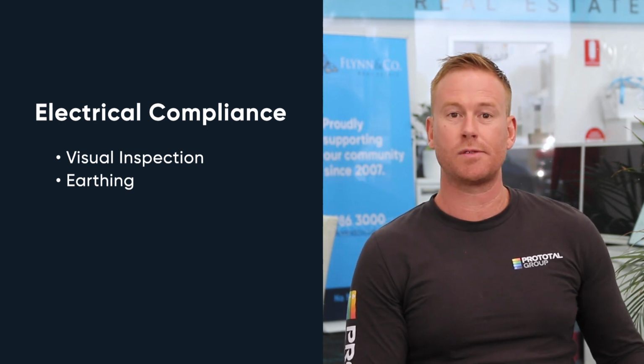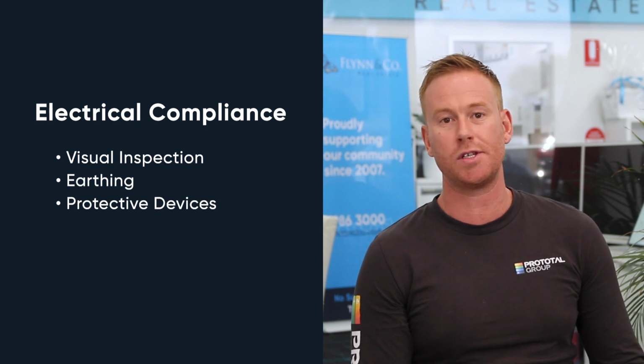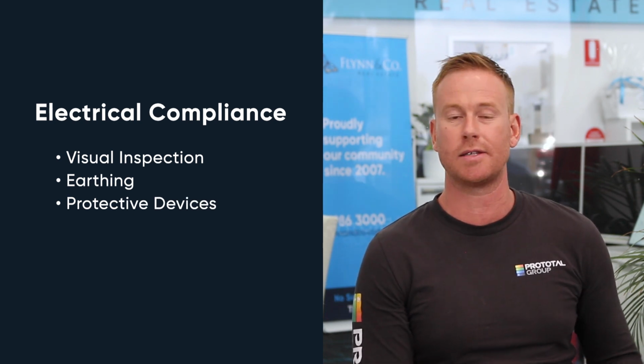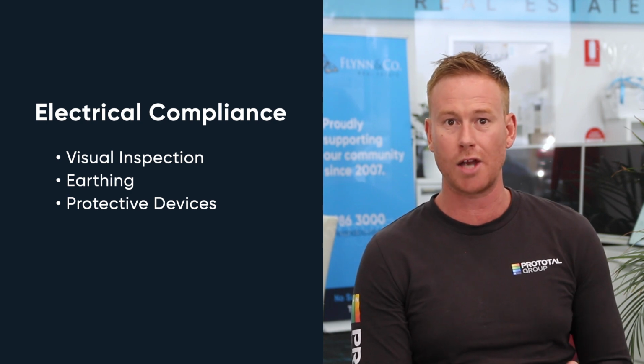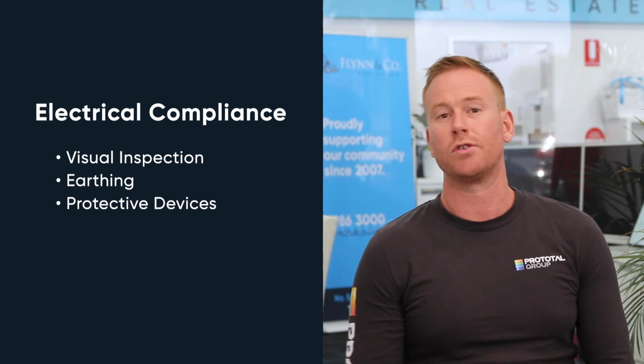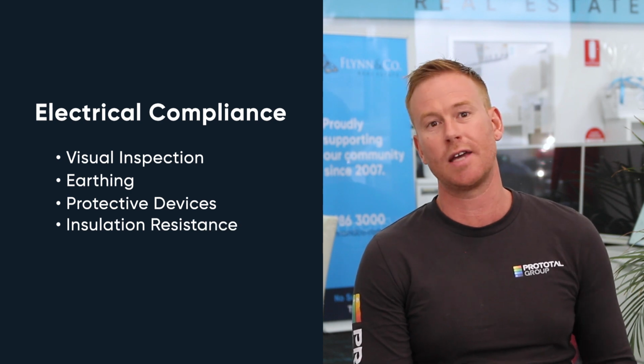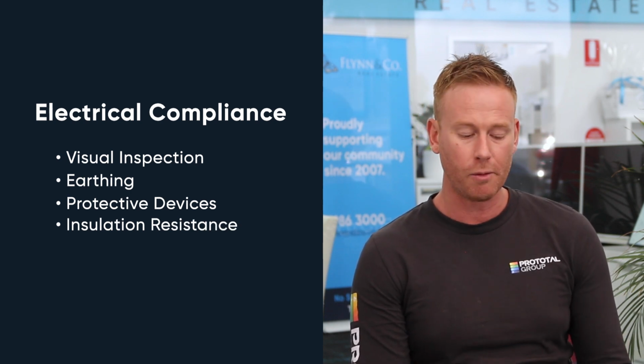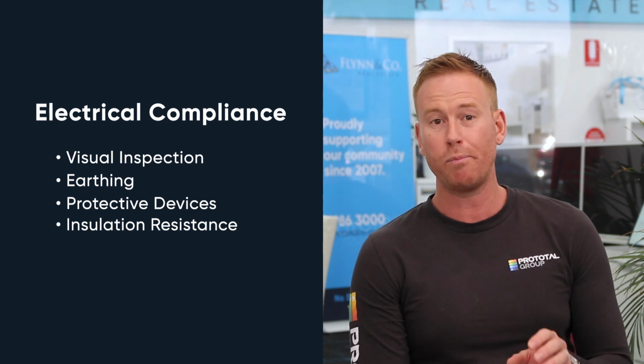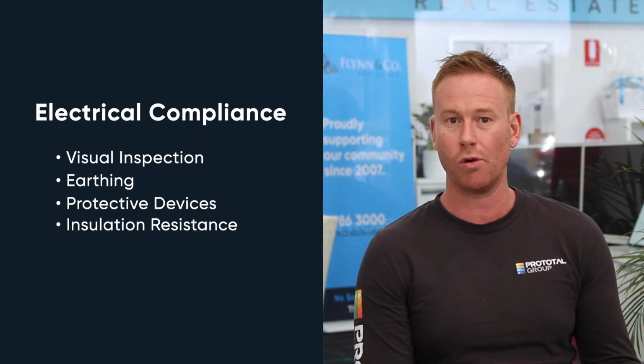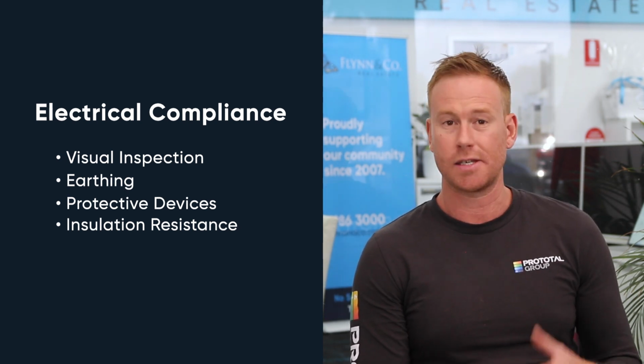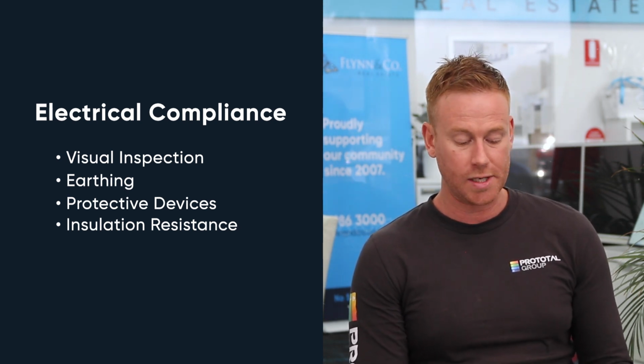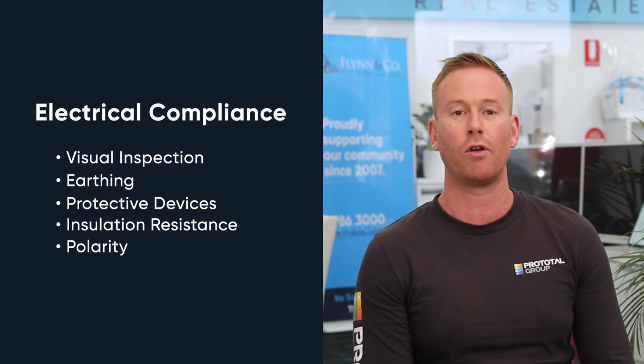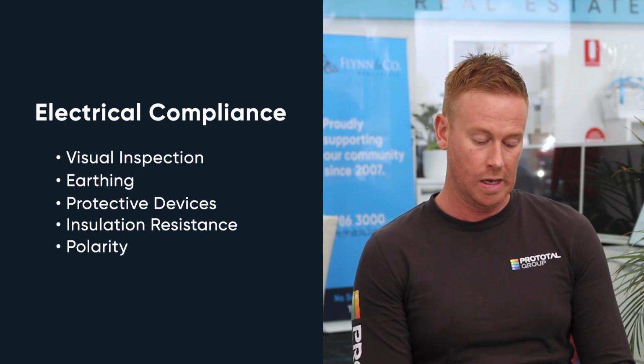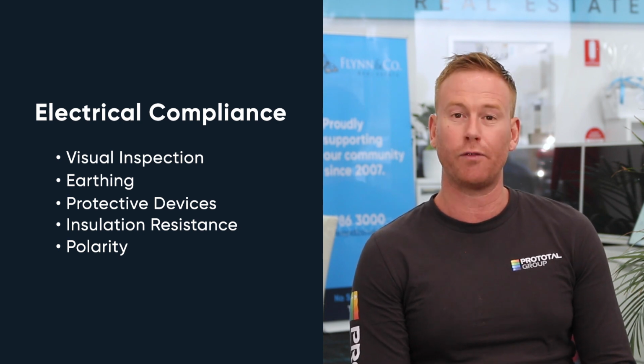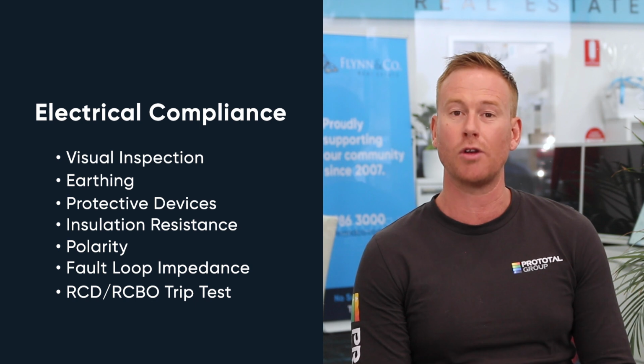We run through a number of steps: protective devices, your safety switches, circuit breakers, the integrity of those, and the related tests. We also do insulation resistance testing to test the integrity of your existing cabling, making sure that there are no weak points that will obviously cause an electrical hazard. Our testing equipment will pick that up. We check for polarity, correct wiring on all of the circuitry, and we do a number of tests for fault loop impedance and RCBO trip testing.